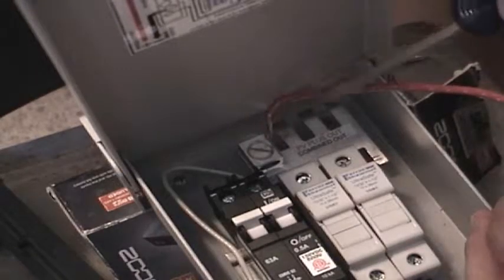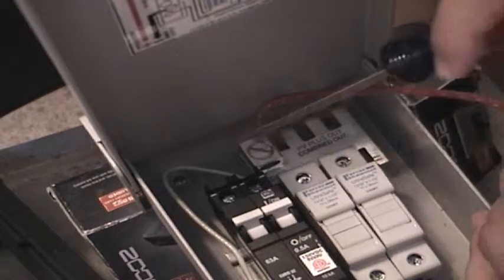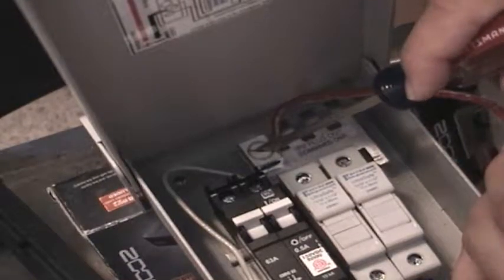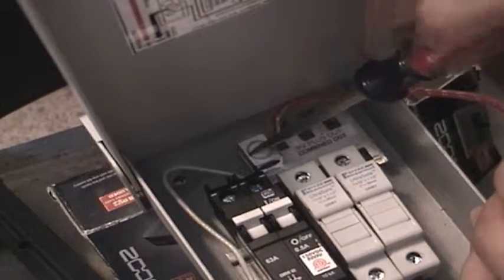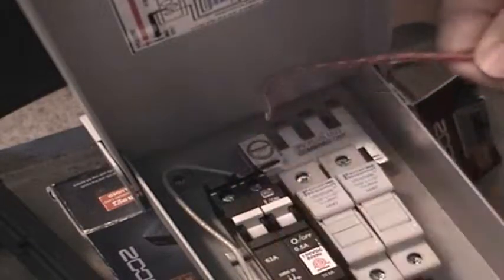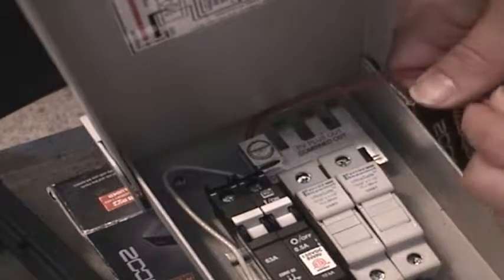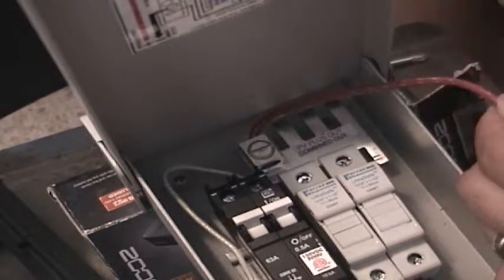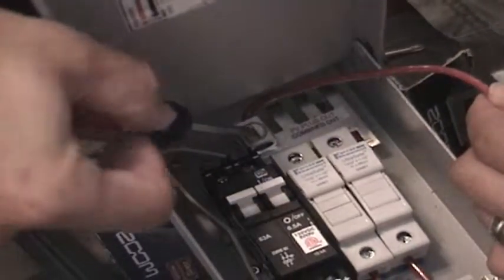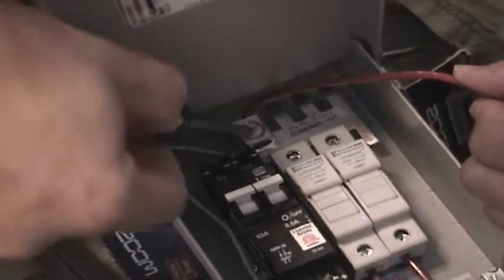Now let's take one end of the red 10 gauge cable that we just cut, and we're going to secure it to the PV out bus bar. So let's loosen that top screw. Then let's slide that wire into the hole. Let's tighten down that screw. Make sure again that there's no bare wire exposed. Secure down that screw as much as possible.